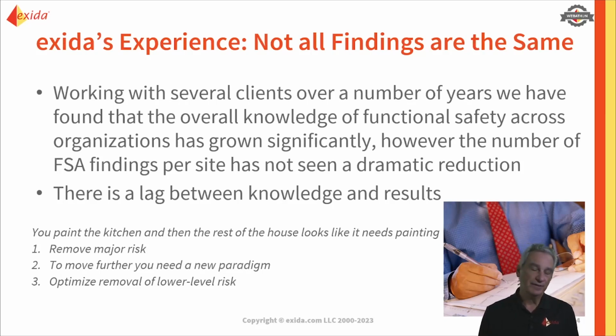So for example, with the Functional Safety Assessment 4, the period of time is not defined, but we could use the 5-year revalidation window between doing our hazard and risk assessments, because 5 years should be a reasonable amount of time to gather field data, to do some proof testing, for example, to gather information on our cybersecurity and gather information on our alarms, for example, and our operational procedures, and then use that information to feed into the next revalidation. So that could be a reasonable window.